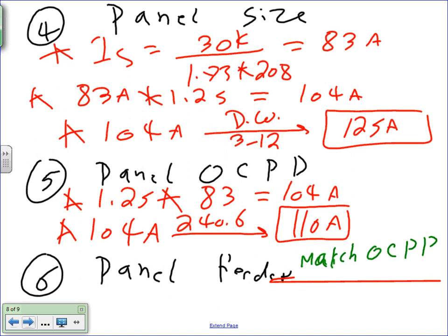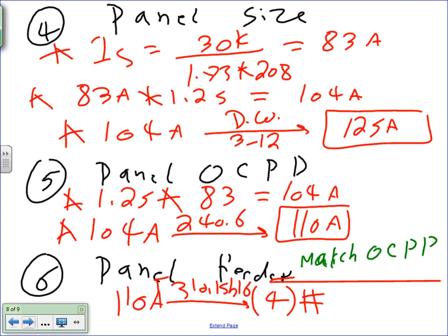So for the panel feeder, I say match the overcurrent protection device. In my case here, if I'm to match the overcurrent protection device, I need to take 110 amp to table 310.15 B16, and that will get me 4 conductors. Why 4? I have a neutral now. And number 2 AWG. Can you check that it's number 2?